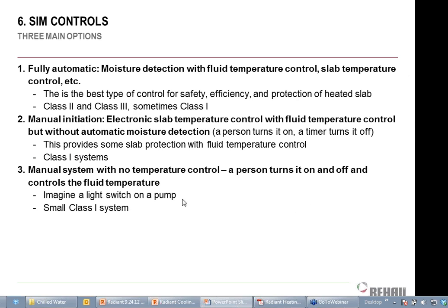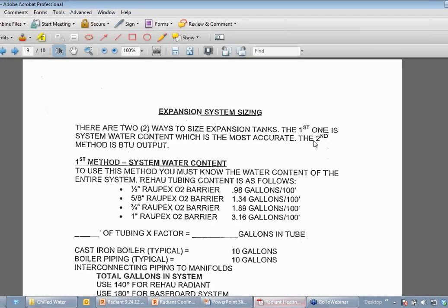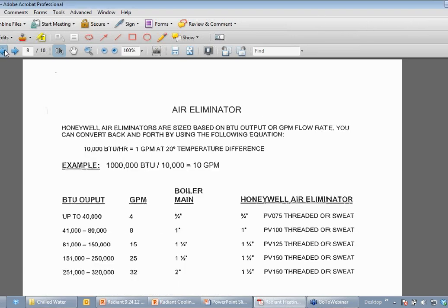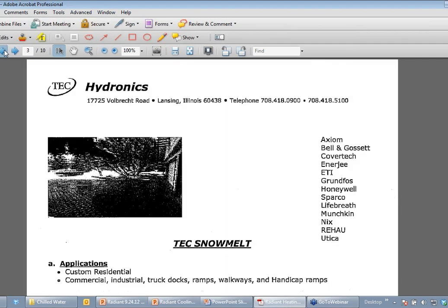Robert's second question is, what is the typical water supply temperature for a snowmelt system? The snowmelt system does not need to be very hot. It's not like I need to send 180 degree water out there. Let me see if there's anything on Bill's cheat sheet, but it's very common that you'd have water, 60 degrees or something like that. It doesn't need to be very high. Let's see if he put anything on here for the snowmelt page.